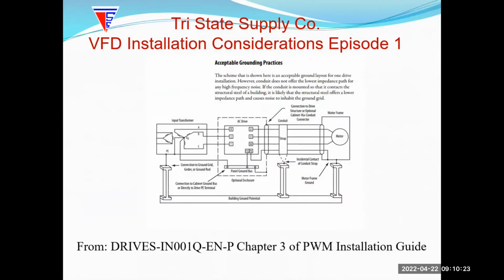Here's a typical installation. We have our transformer, which here is a Y neutral ground. You got your drive panel with your drive, and you got your motor and the cabling. Now, the one thing we want to try to do is get everything on this ground plane to be the same potential, and also have a path back to the drive, because that's the source of any of your noise that's going to be generated. It's going to want to get back to the source, and we want it to get back to the drive the shortest distance path it can.